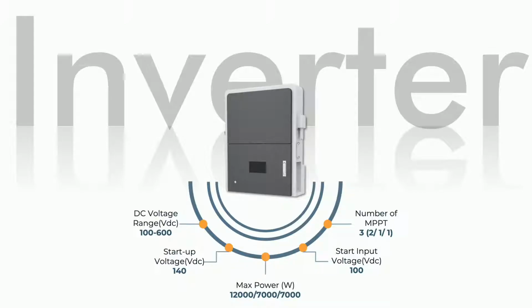As the specification shows, the DC voltage range is between 100 to 600 volts, and the startup voltage is 140 volts. The max power is 12,000, 7,000, and 7,000, which is related to the number of MPPT, because this is a 3-phase inverter. The number of MPPT is 3, 2, 1, 1, and the start input voltage is 100 volts, which means that if the voltage reaches 100 volts, you can start the machine, but it cannot discharge.